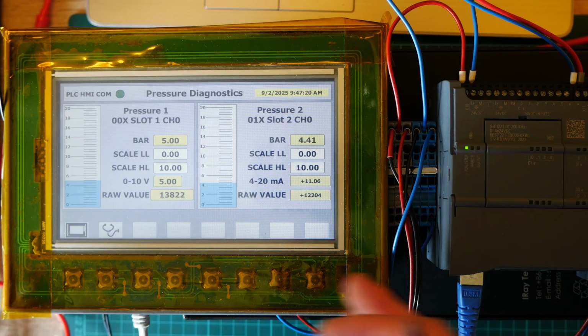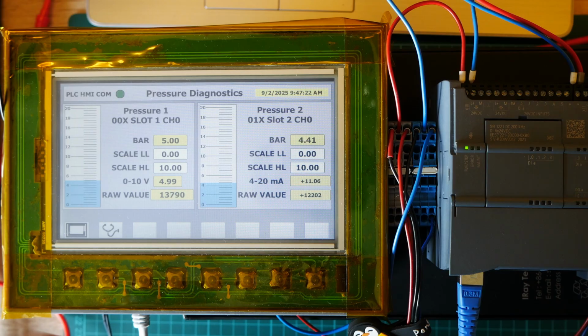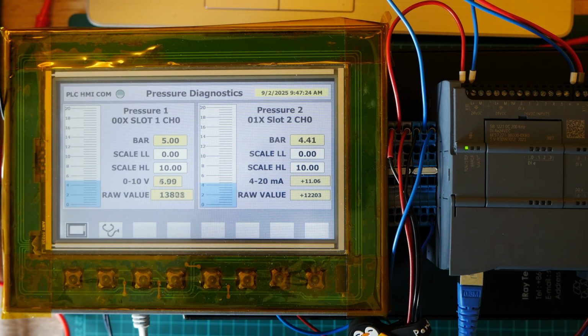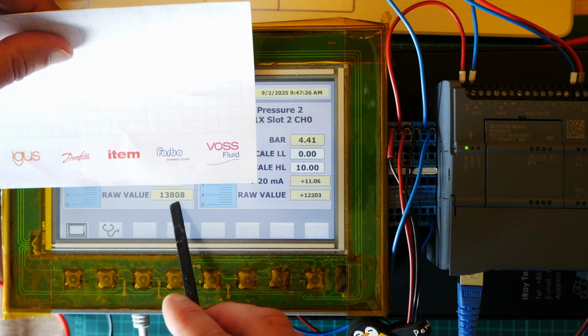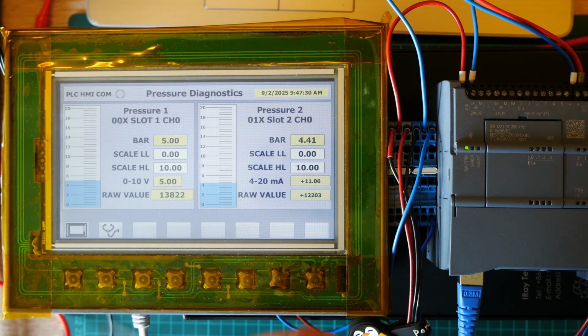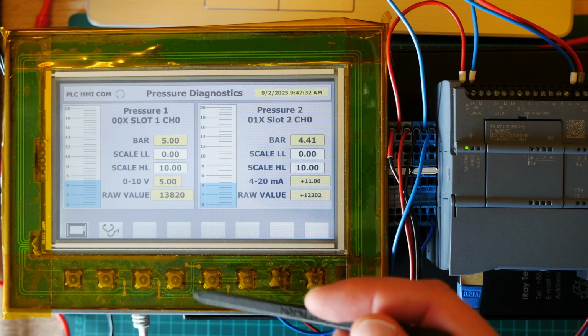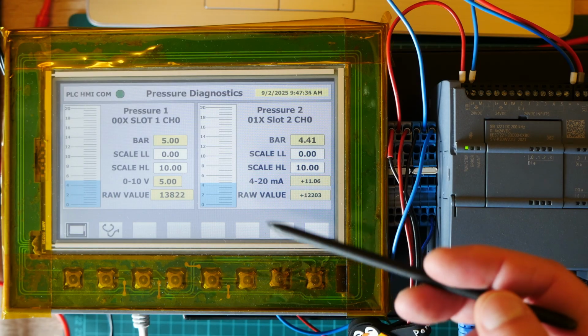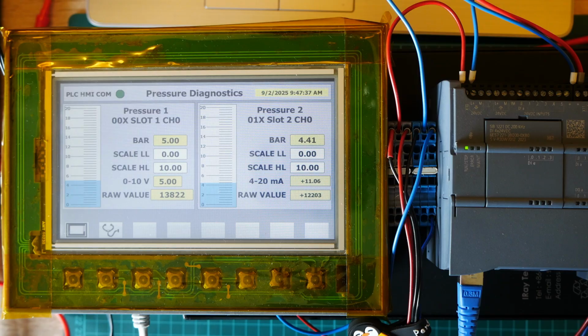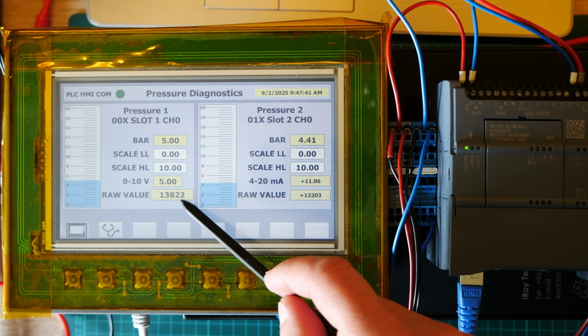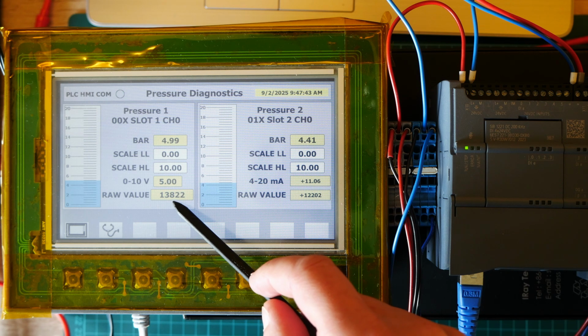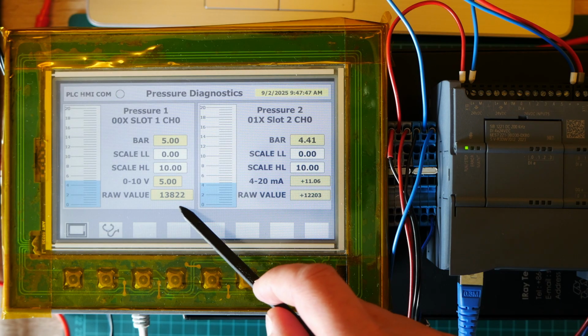So if you have this screen, fine. If you don't have it, you should ask to make one. If you have something like that, right now I'm looking only at the raw value of the sensor. So 0 to 10 volt transducers and the line are susceptible to interference. And as you can see, the raw signal is jumping. But this is actually kind of normal.